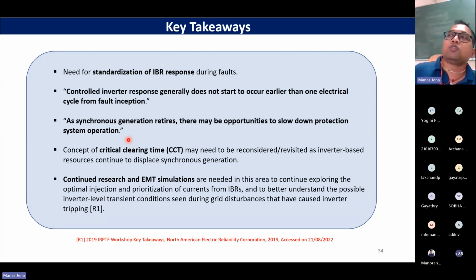See, why we used to clear so quickly? It is related to what? Transient stability, right? Critical clearing time. So now that we are replacing the synchronous machines, there is a question mark. That is a very interesting question. Can I slow down the protection? Do I really need to clear the fault within 5 cycles? Question mark. I am not saying yes we should do, no we should not do, question mark, which is again coming from this workshop. The concept of CCT may be revisited.